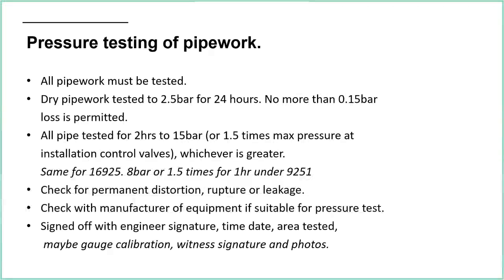But if you're doing an air test, there's no mess. If you come to do a hydrostatic test and find you've got an open end, then you've got a little bit of cleanup to sort out there. So yeah, an air test is a good idea to do first. Little note here about checking with the manufacturer of equipment if suitable for a pressure test. On the one hand, this is common sense, in both respects, really. Yes, it's common sense to check, but why is there equipment on there that is not suitable for that particular pressure test? They're both relevant points.